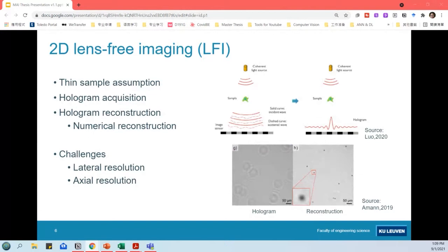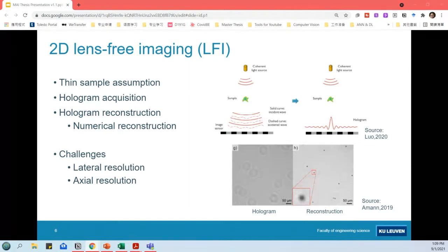Let's have a quick look at the basic theory of 2D lens-free imaging. This theory assumes the sample to be a thin layer of materials and requires two steps. The first step is hologram acquisition: the sample is illuminated by a coherent light source, generating an interference pattern between the incident wave and the scattered wave. This pattern is called a hologram and captures both amplitude and phase information of the sample. In the second step, we use this hologram to reconstruct the original representation of the sample with numerical reconstruction.